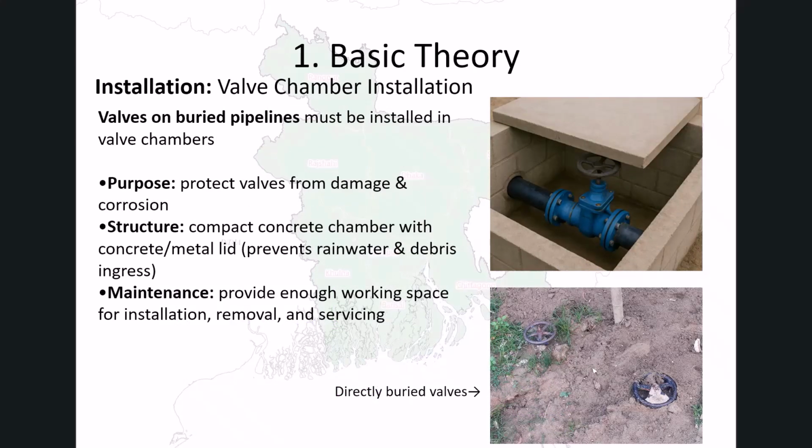Underground valves must be installed within valve chambers to protect them from corrosion, soil intrusion, and external impact. The chambers should be equipped with durable covers and provide sufficient space for inspection and maintenance. The photograph in the lower right shows an example of a valve that has been directly buried. In this condition, excavation is required for maintenance, and continuous contact with soil can lead to corrosion and long-term deterioration of the valve.